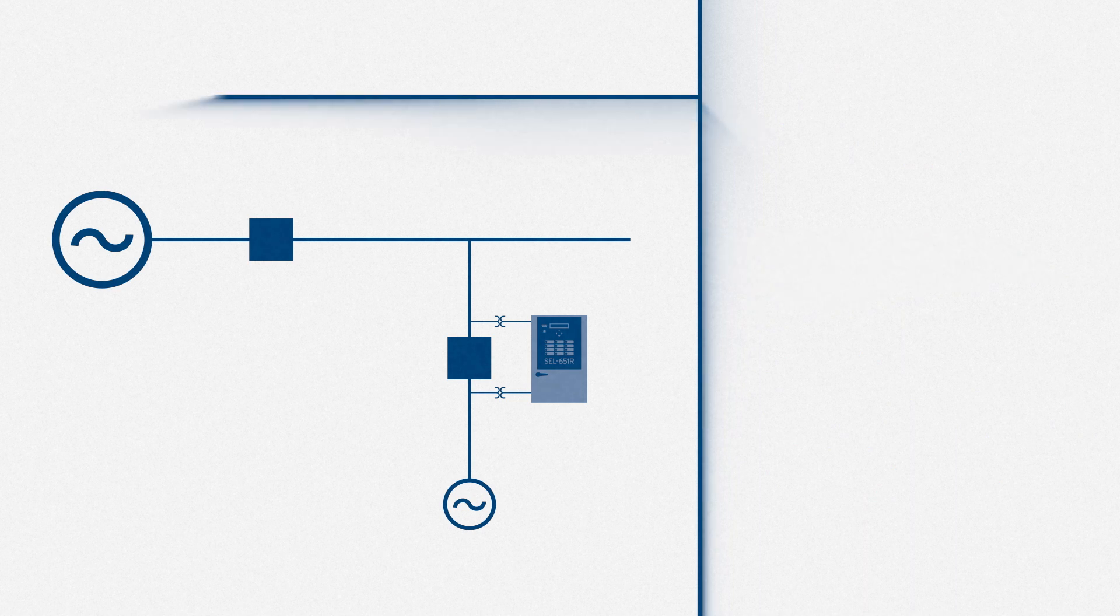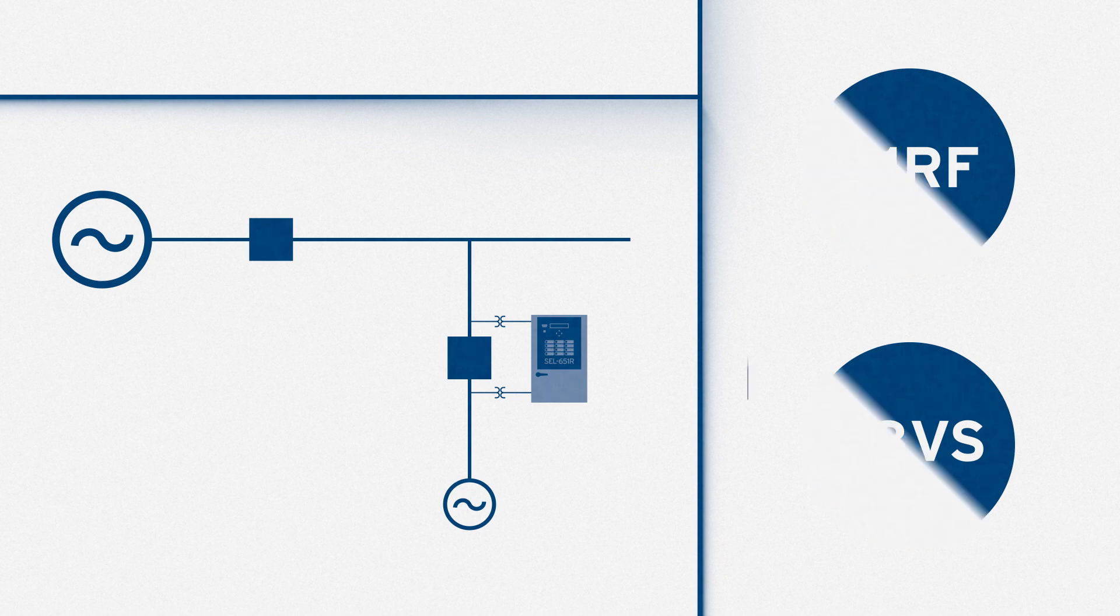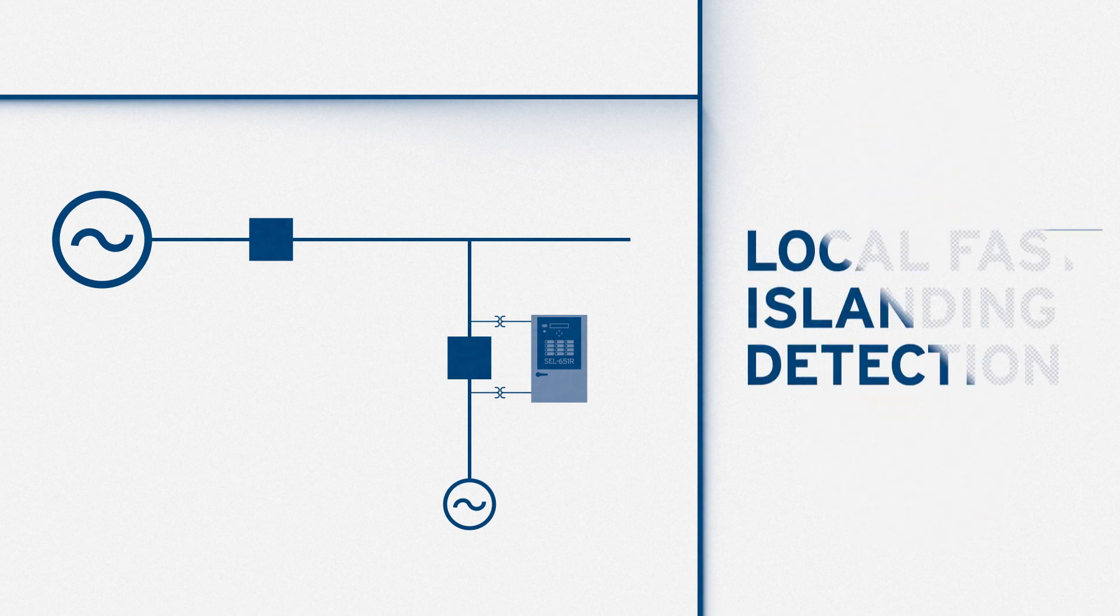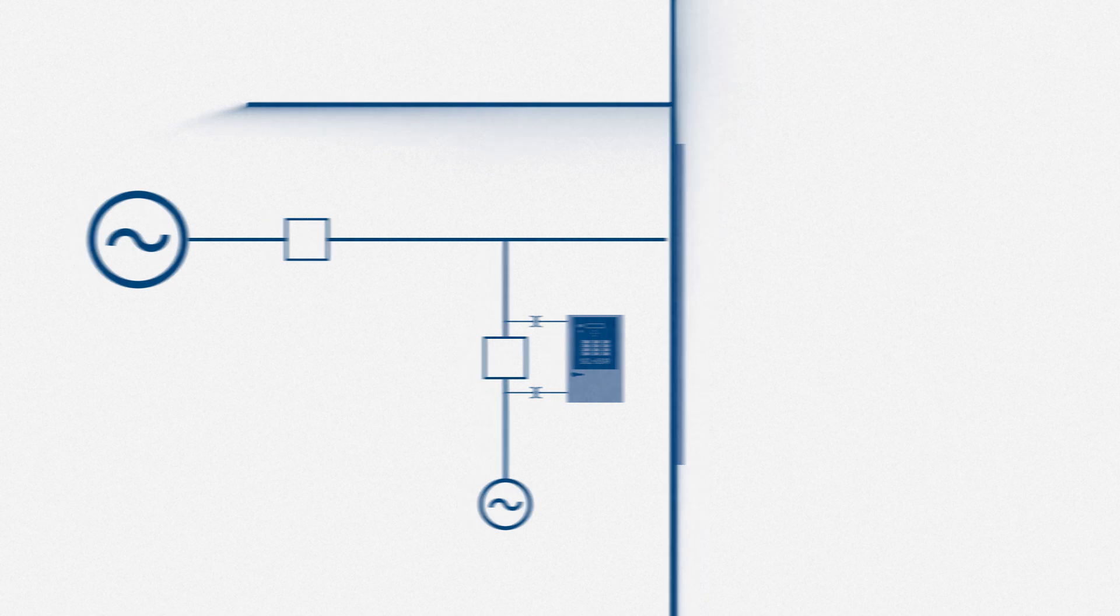In addition to the traditional phasor-based islanding detection, we built specific protection elements into the SEL651R so now it can also perform local fast islanding detection.